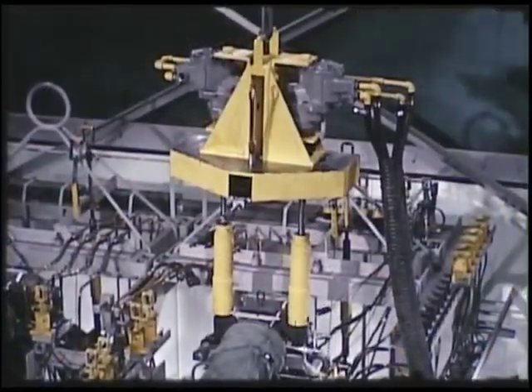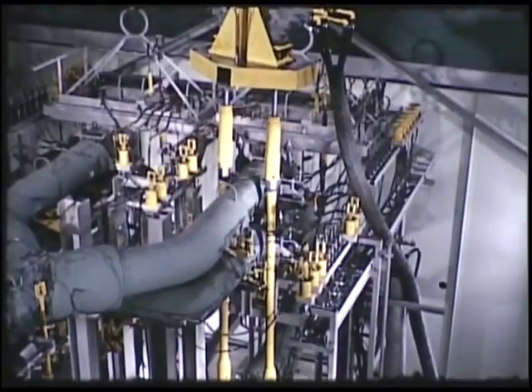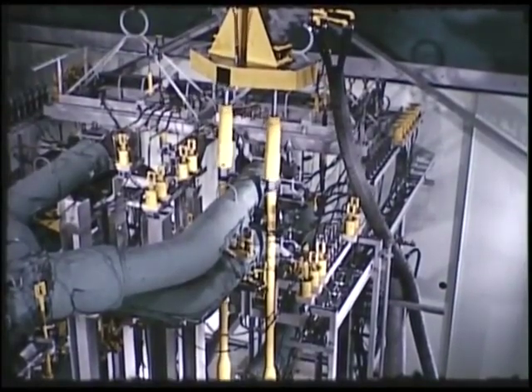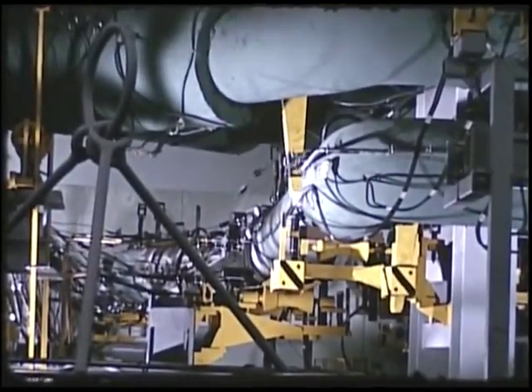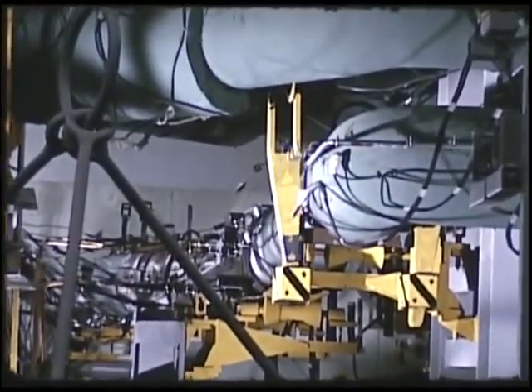Once again, the special tool is used to loosen the flange clamp bolts. The bolt runner unscrews both bolts in each clamp using socket extensions on the lower clamps. Wedges are installed to hold the pipe in position on the sliding spring supports during the jack screw loosening operation.